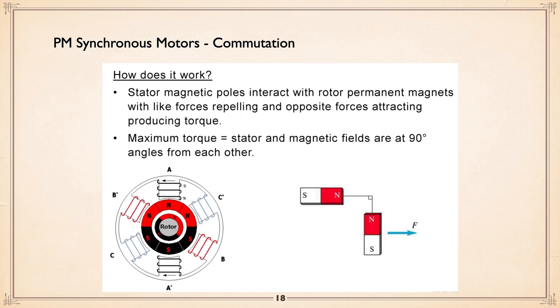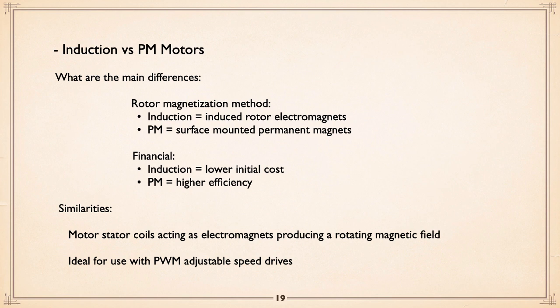Now, maximum torque is when the magnetic fields are at 90-degree angles from each other. But basically, there it is. When the motor is operating, it rotates at the same speed as the field does. The difference between induction motors and permanent magnet motors is how they do it. In an induction motor, you're inducing power in the rotor, which then creates magnets, because there are electromagnets as part of the deal. With permanent magnet, you're using surface-mounted permanent magnets. Financially, induction motors are cheaper. Permanent magnet motors are higher efficiency, but they operate the same way. And adjustable speed drives work just fine with permanent magnet motors.